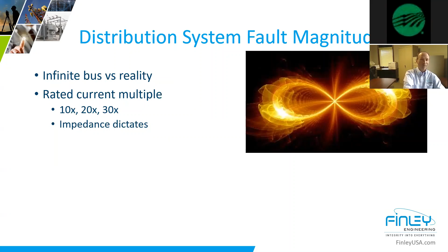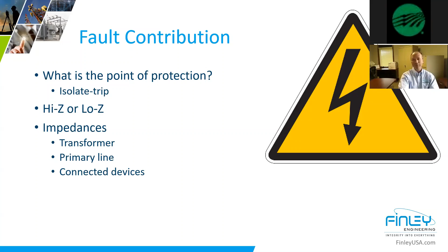This is another interesting point that a lot of people don't grasp. What is the point of our protection in general? Well, we want to generate massive fault current quickly to trip protected devices. That's protecting the public. We want to isolate as fast as we can and segment as much as we can to limit the impact, and that impacts our safety and all those metrics. Everything connected along the way is going to change that parameter for us.